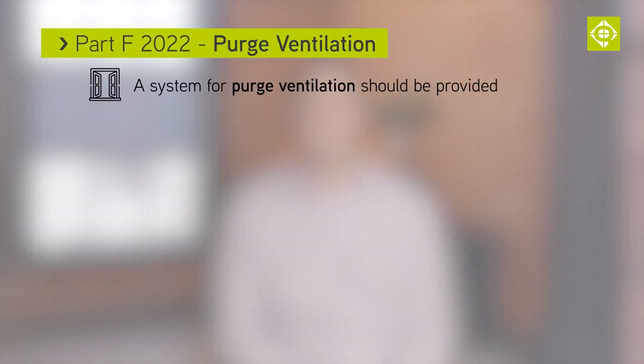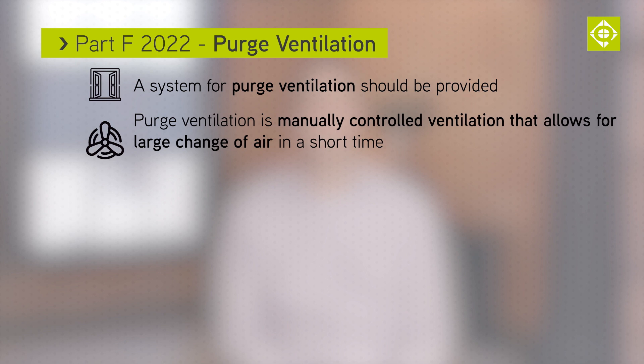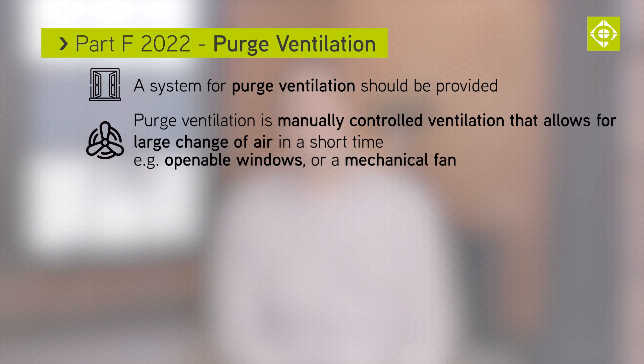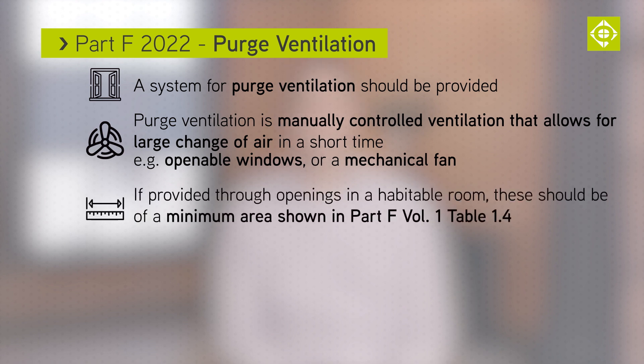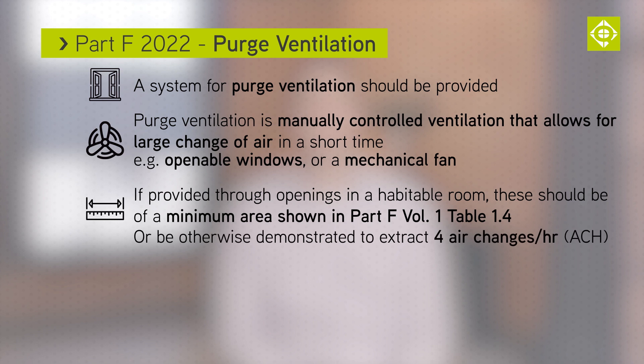A system of purge ventilation should be provided. Purge ventilation is manually controlled ventilation that allows for a relatively large change of air in a short period of time — for example, opening windows or a mechanical fan. If this is provided through openings in a habitable room, these must be of a minimum area shown in Table 1.4, or otherwise demonstrated to provide 4 air changes per hour.